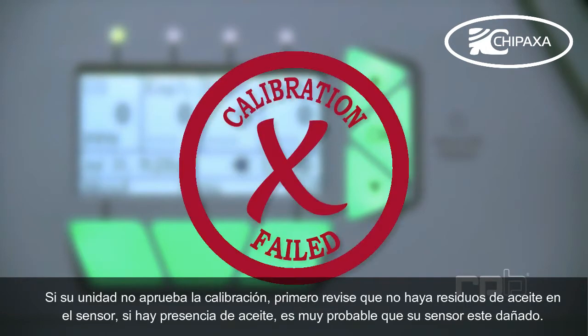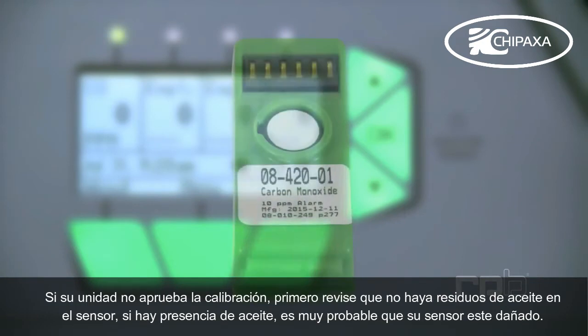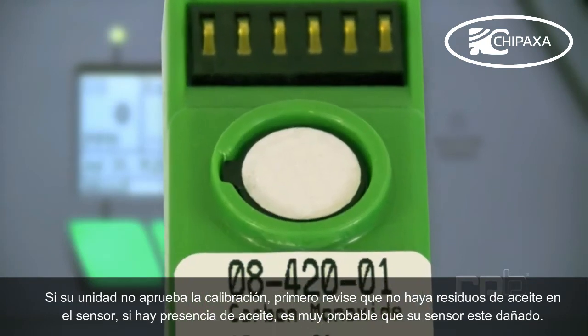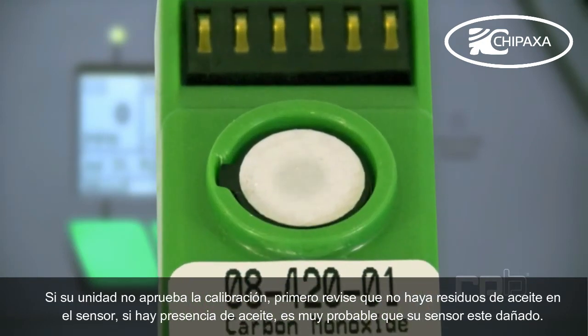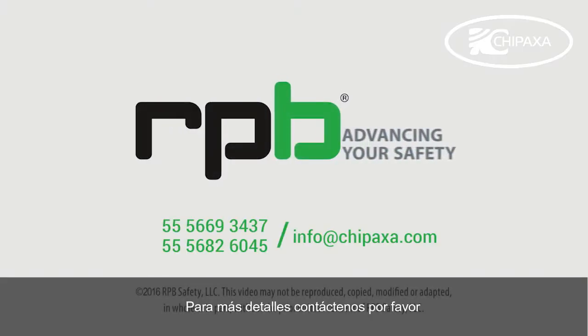If your unit fails this calibration, first check the sensor for any oil residue. If there is oil present, it is likely your sensor is damaged. For more details, please contact us.